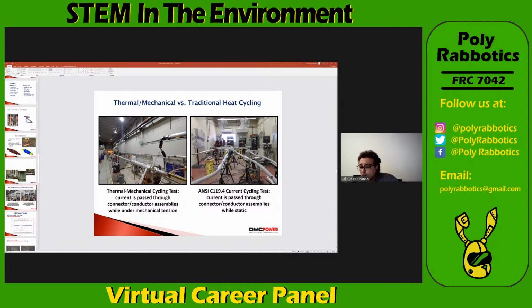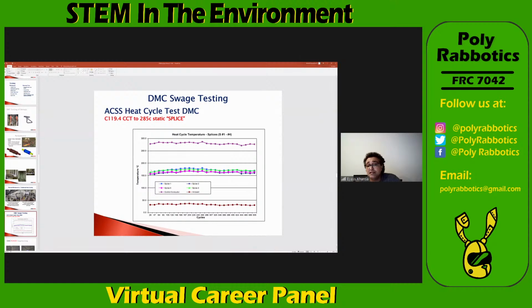To the right, this is what we call the current cycle test. You heat the fitting to almost 275 degrees Celsius, and then you cool it down. You heat it and cool it down to simulate the life of the fitting over 20 years. Every time you take a measurement of resistance and temperature, and if it is stable, that means the connector is good.